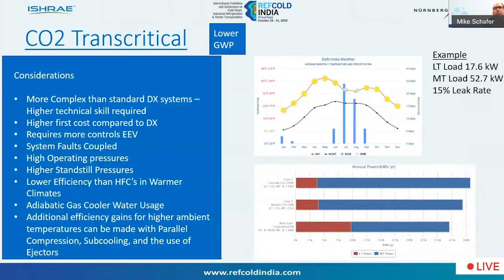So what are the considerations? In general, CO2 transcritical systems are going to be more complex than the standard DX systems, and therefore require higher technical skill for installation as well as maintenance. And generally speaking, there's a higher first cost as compared to DX, although component costs have been coming down over the last few years. A lot of activity in Europe in terms of developing systems. As I mentioned before, it requires more controls or EEVs. High-side equipment also has a lot of controls.